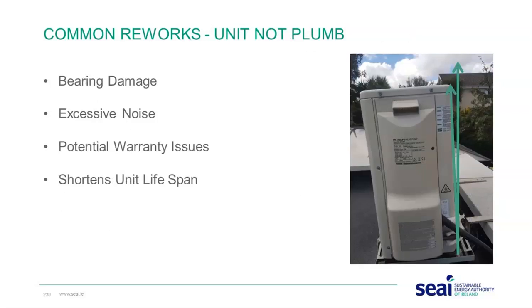Another thing that we would come across is where a unit isn't plumb. So not specifically leveled, we're more looking at the plumbness of the unit. Our concern is bearing damage. So the fan unit's going to have excessive wear and excessive noise. Potentially the warranty may be shortened, and the overall lifespan of the unit could be shortened. So again, this is something that we'd ask you to go back to the site to fix.